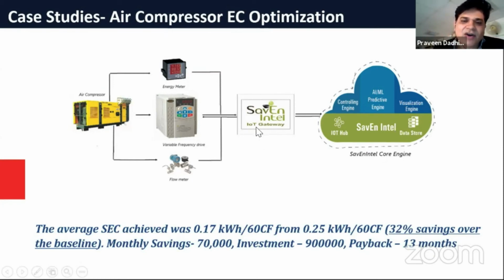In the conventional energy method, we would typically deploy a VFD without much data, giving around 15% savings. But since we had data, we ran artificial intelligence and machine learning modeling on it, coupled with energy engineering, to design a program for the VFD that would run the air compressor at its best efficiency point 24 hours a day. Through analytics we identified zones where the compressor ran at very low, moderate, or very good efficiency, and we were able to decide what frequency to give the compressor so it runs at best efficiency all the time.